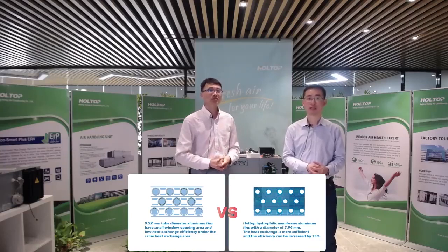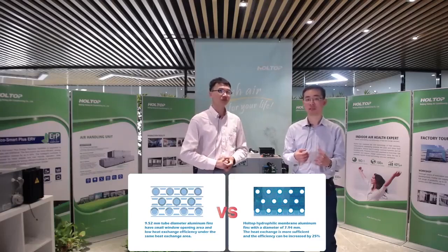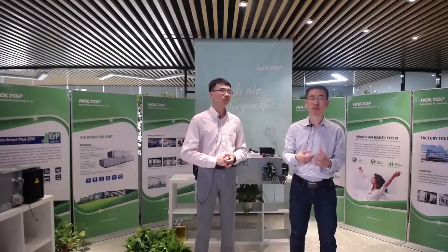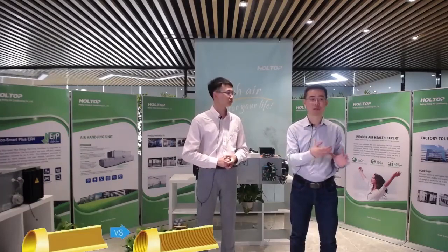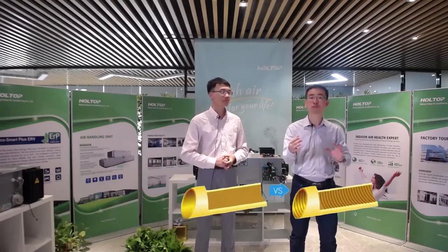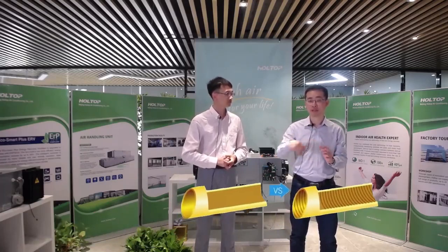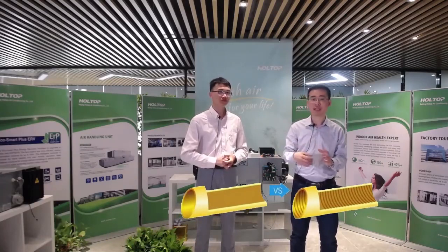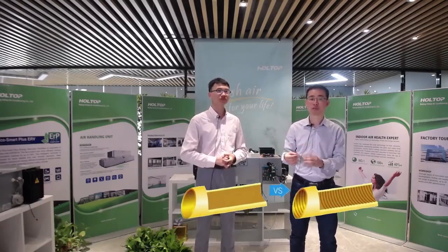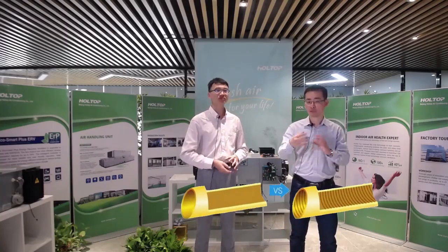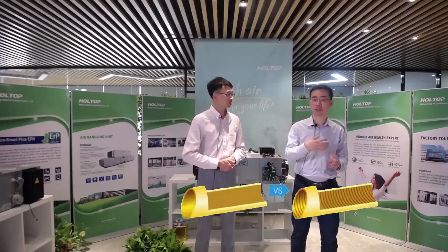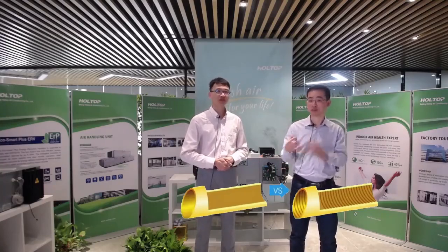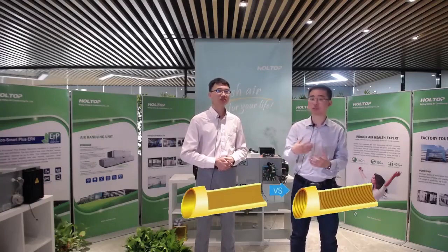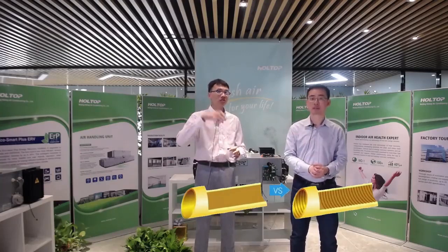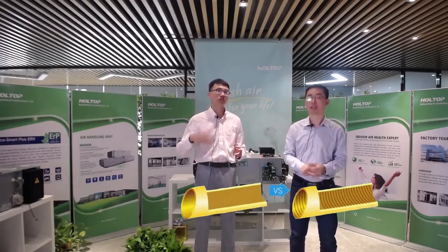Yes, and the copper tube has an internal screw type structure, compared to the traditional one, which is just a plain inside of the tube. This internal screw copper tube makes more space for the refrigerant to the coil connection, and in this way it can also improve the heat exchange between the refrigerant and the air. Yes, it is increasing its internal area for the heat exchange.